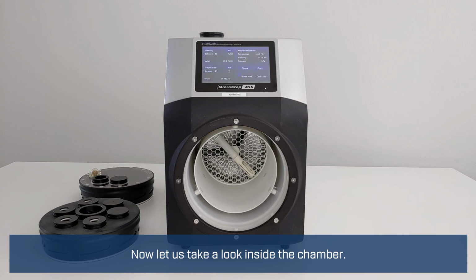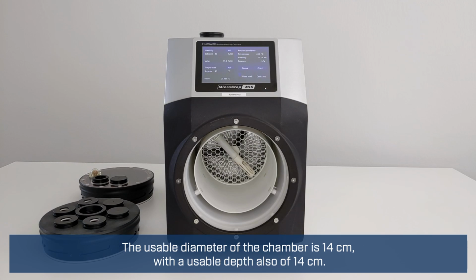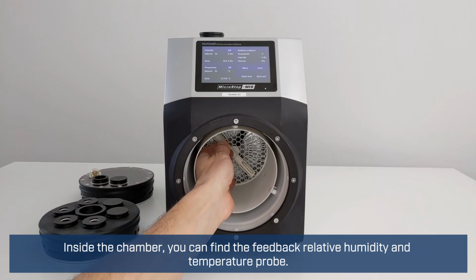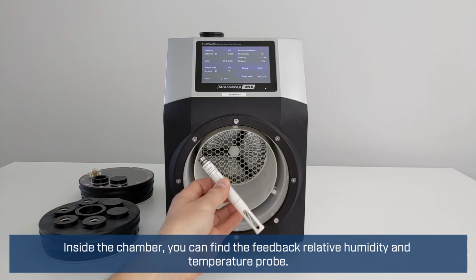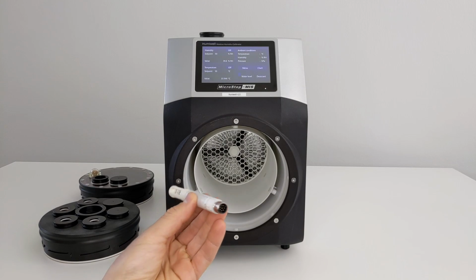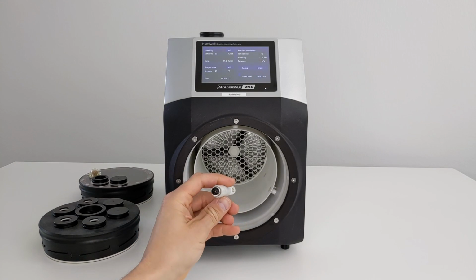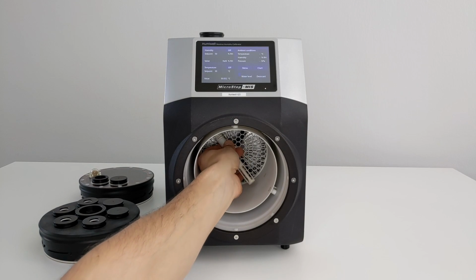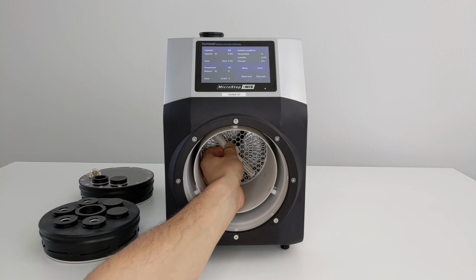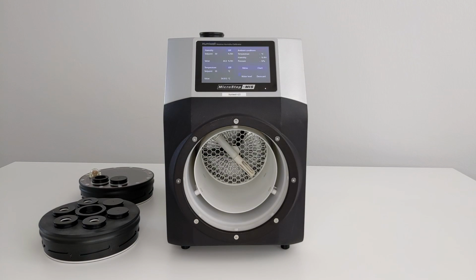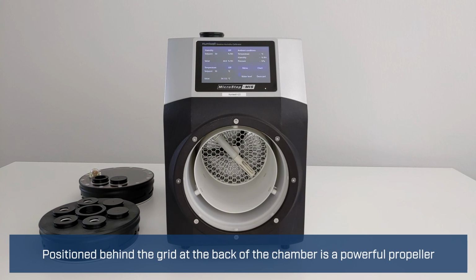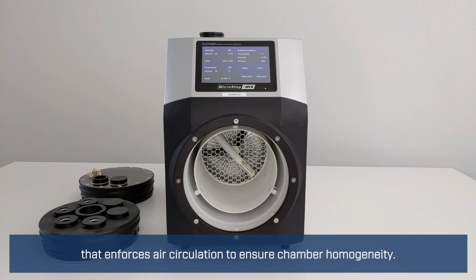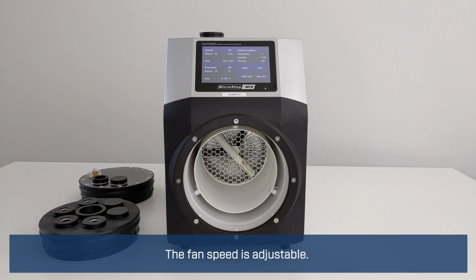Now let's take a look inside the chamber. The usable diameter of the chamber is 14 cm with a usable depth also of 14 cm. Inside the chamber you can find the feedback relative humidity and temperature probe. Positioned behind the grid at the back of the chamber is a powerful propeller that enforces air circulation to ensure chamber homogeneity. The fan speed is adjustable.